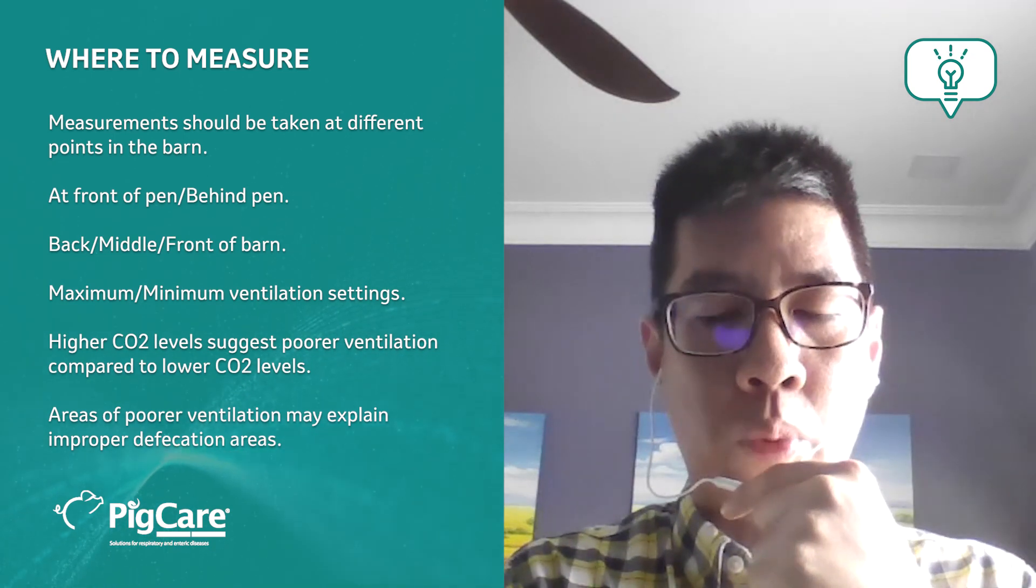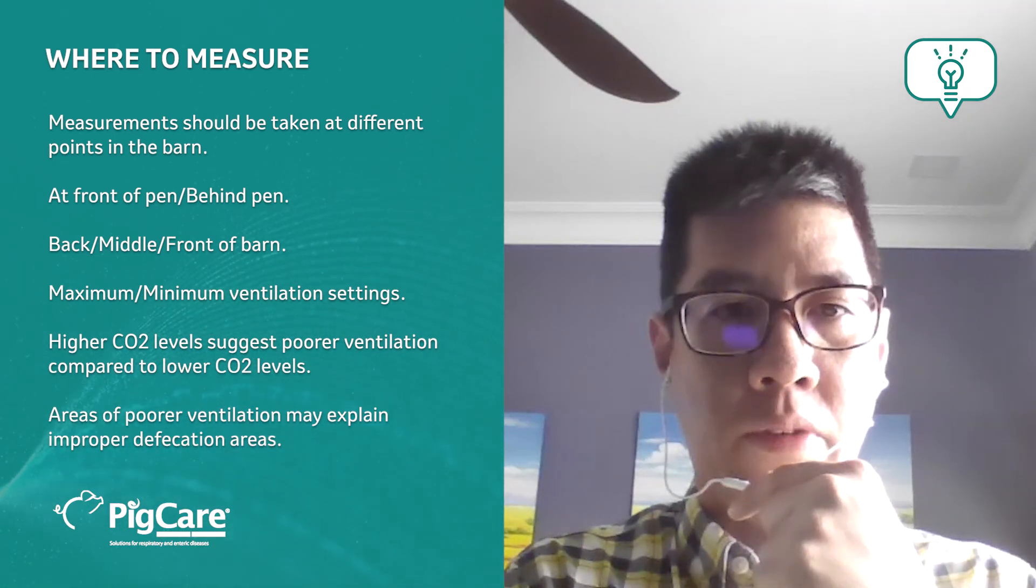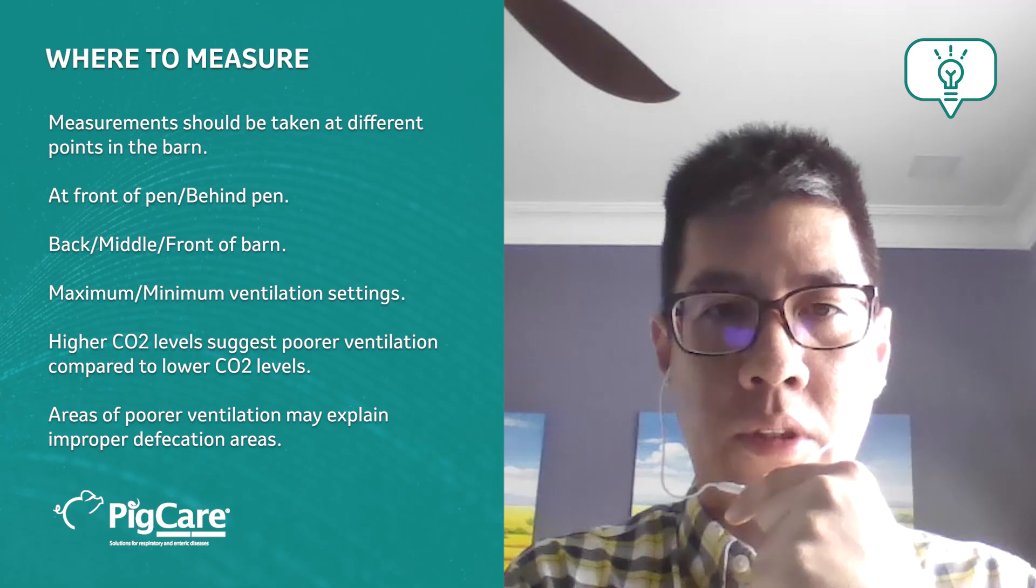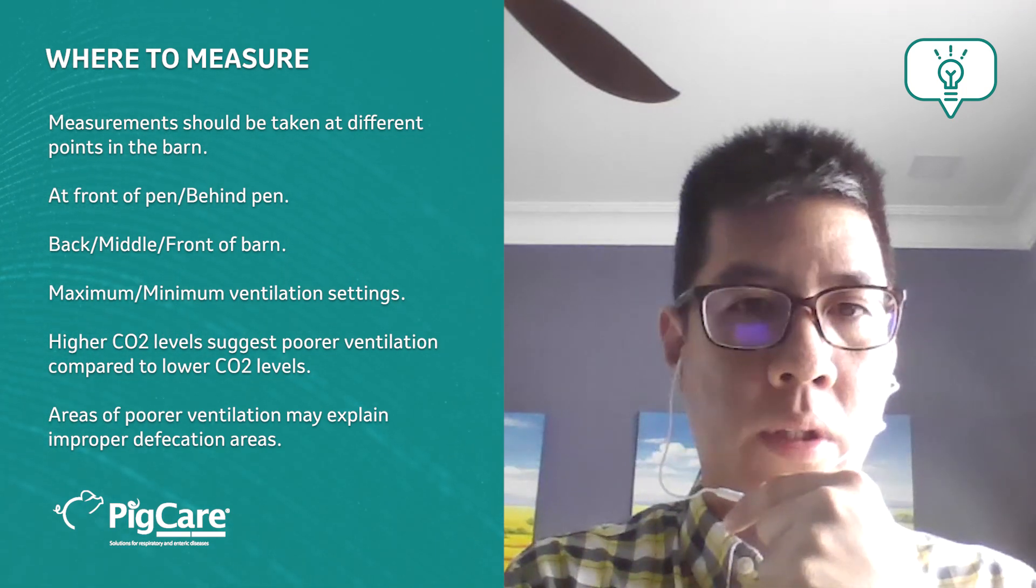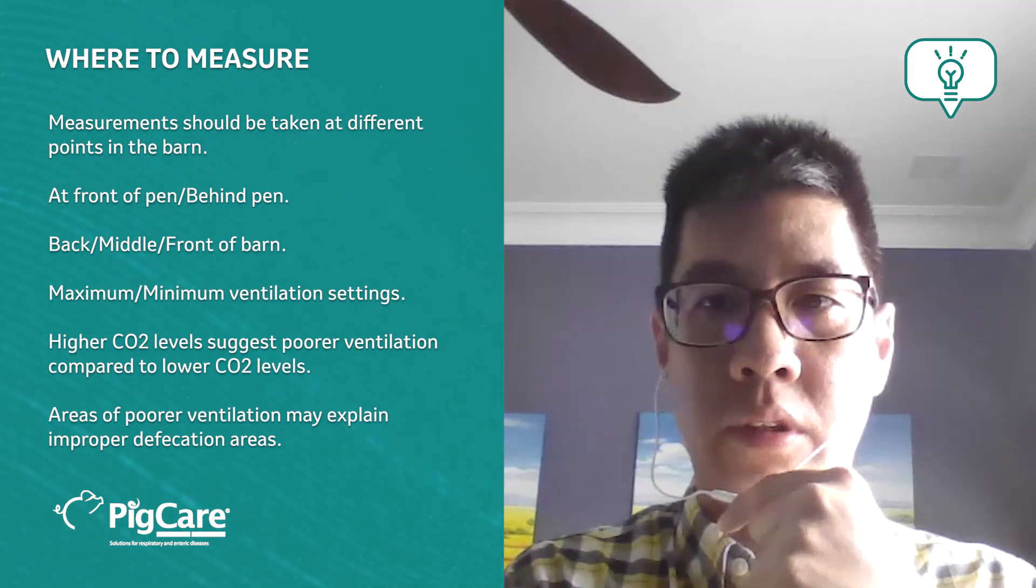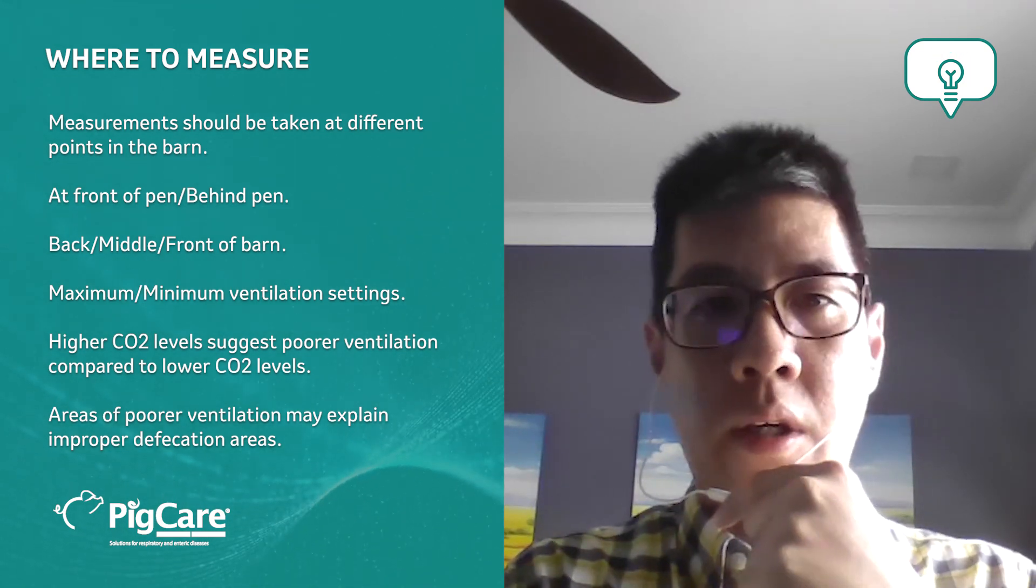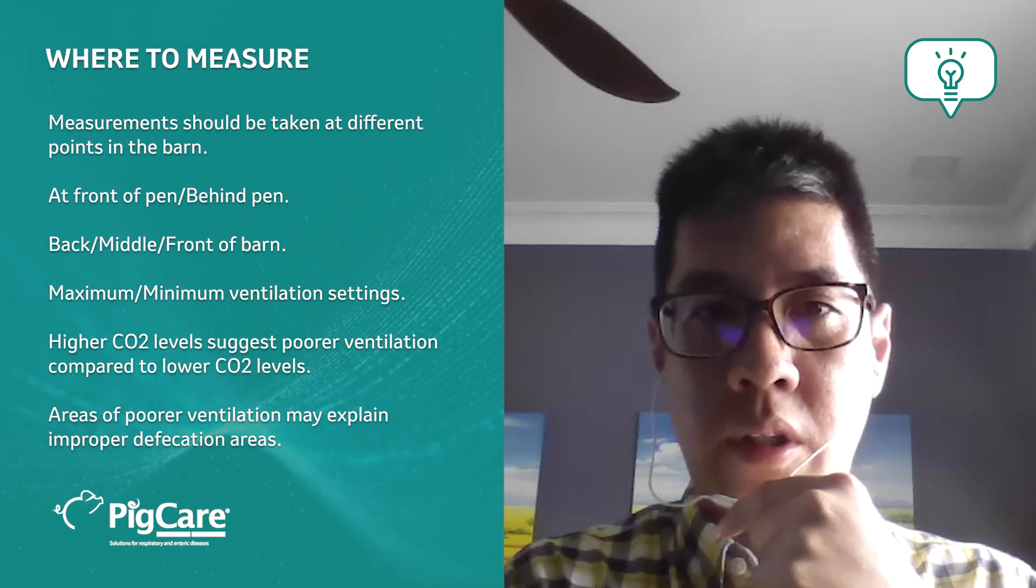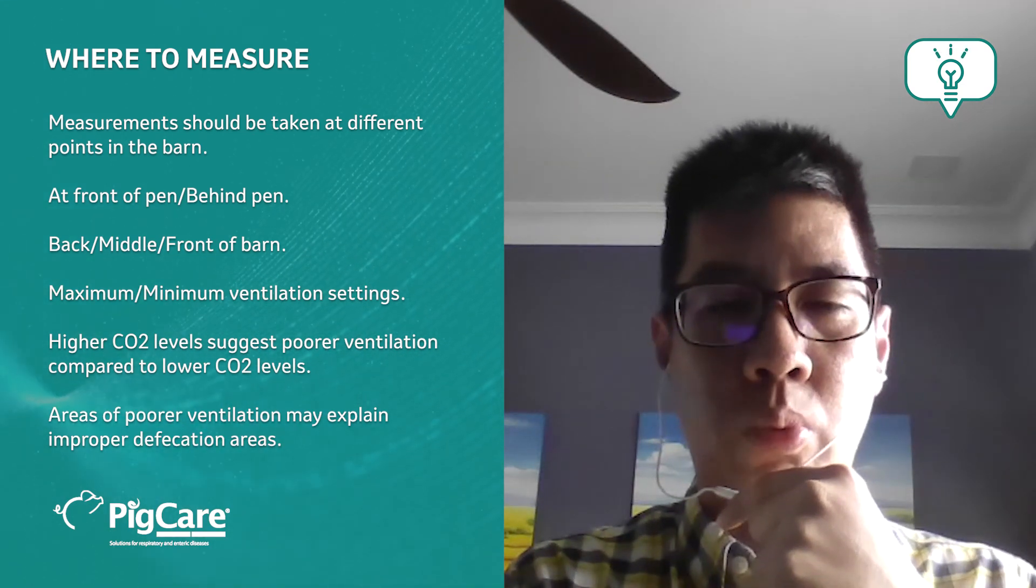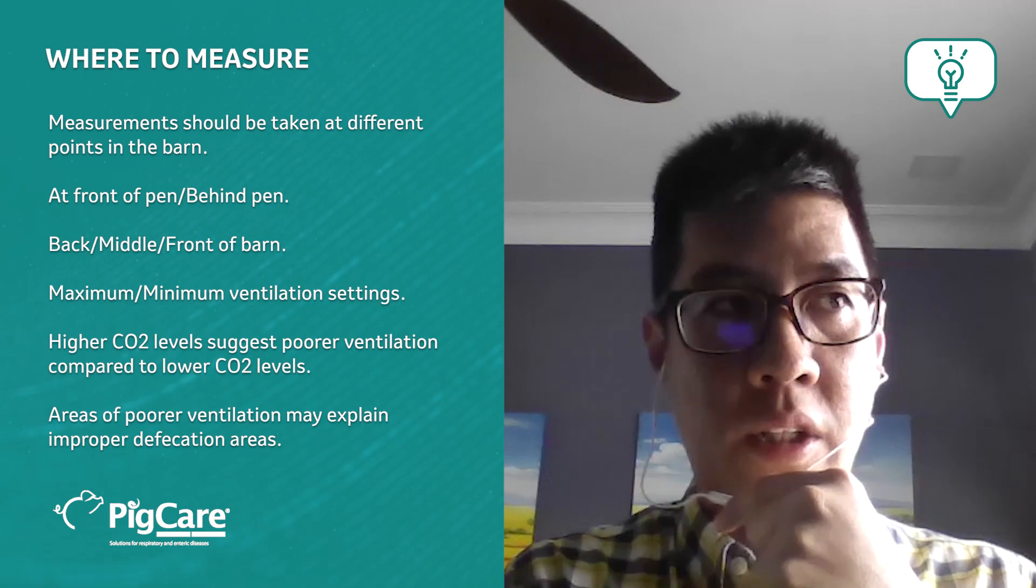We also recommend that the ventilation system is tested at different settings. For example, we can set the ventilation system to maximum ventilation, take a set of readings, and then set it to minimum ventilation and take a set of readings, because we would expect quite a difference in these readings.